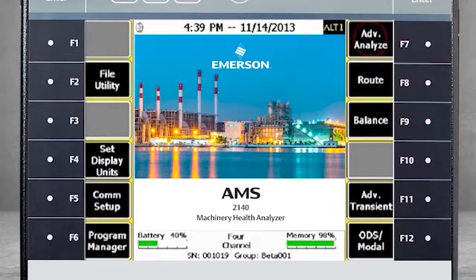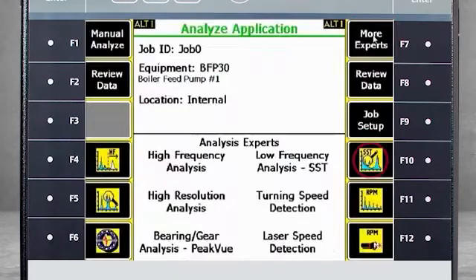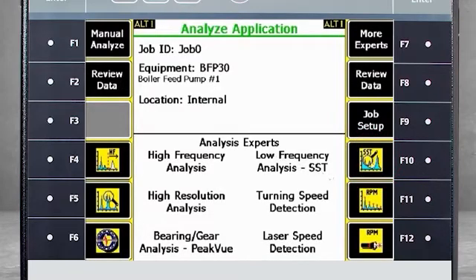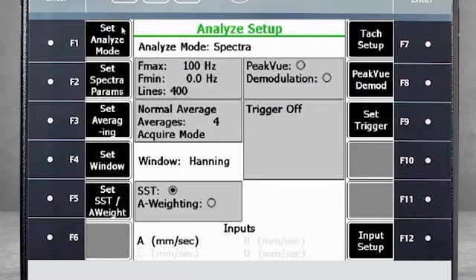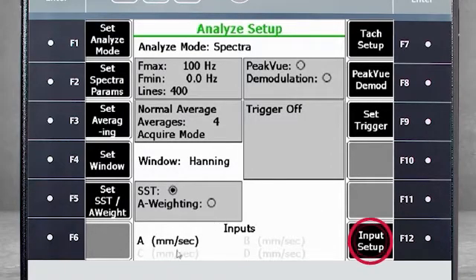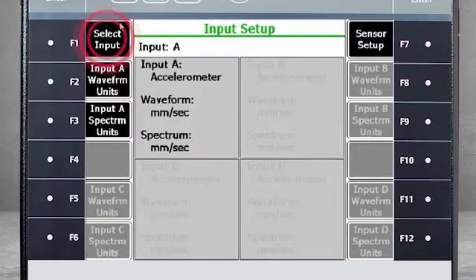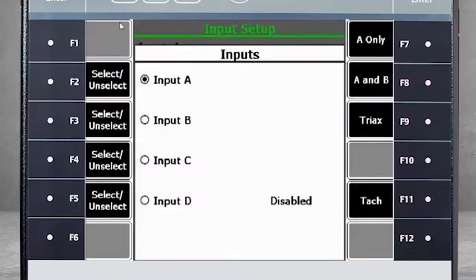From the home screen, select F7 – Advanced Analyze and F10 – Low-Frequency Analysis SST. But this time, instead of starting data collection immediately, select F1 – Manual Analyze. Here you see there is only one input for data. Select F12 – Input Setup, then F1 – Select Input and activate the other channels.